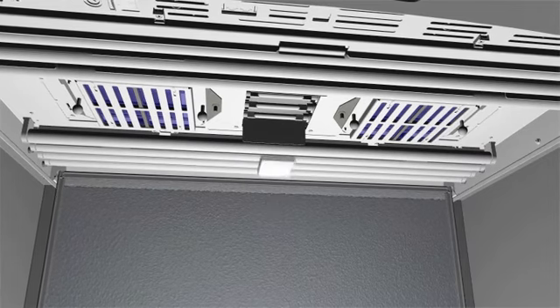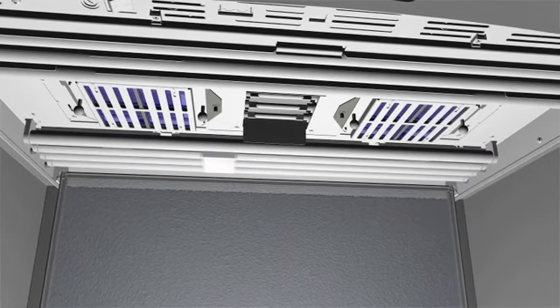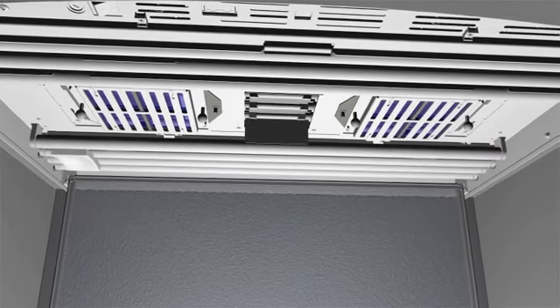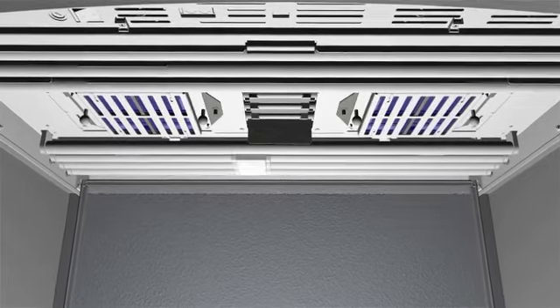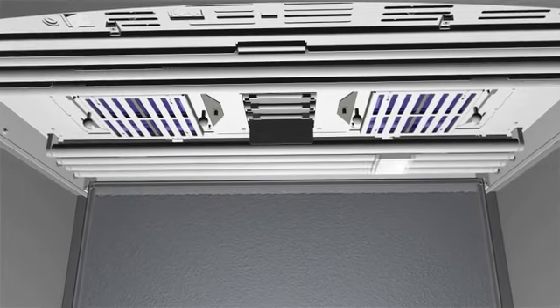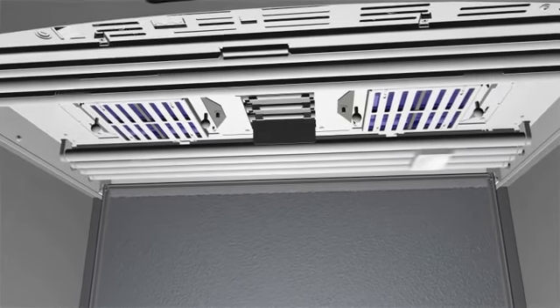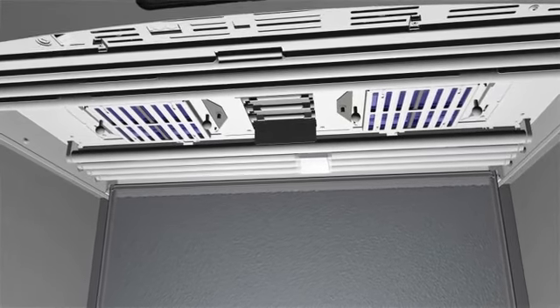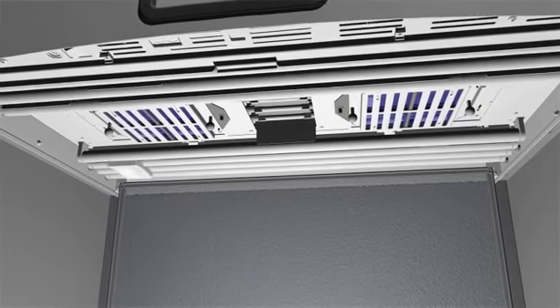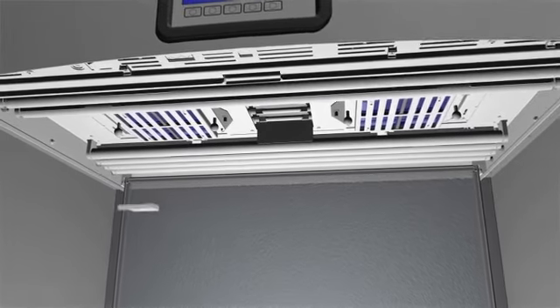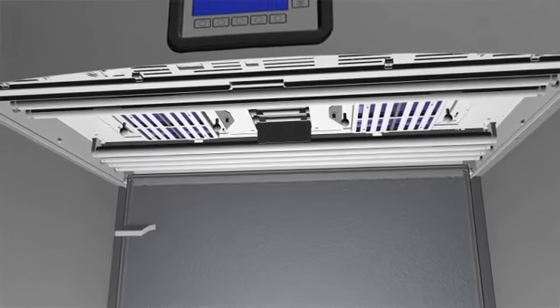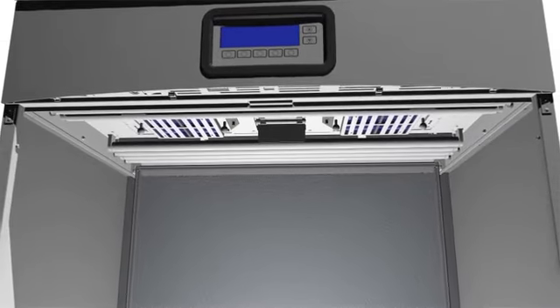Next, clean the fluorescent and halogen lamps. Using a clean, dry, lint-free cloth, remove any dust from the remaining lamps. If there's dirt on the reflectors, use a clean cloth dampened with warm water or a little ammonia-based window cleaner. Allow everything to air dry.